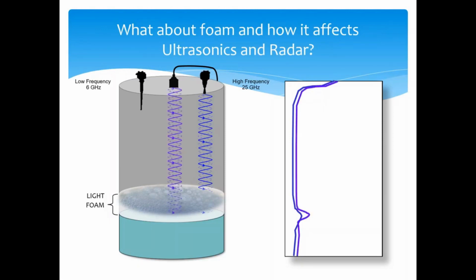When I do ultrasonic, I get a decent signal return here. That's probably a signal that I'd be able to work with. And in both of these cases, we're actually penetrating the foam here and giving you a true liquid level measurement. And then for my low frequency radar, I actually get a very similar signal return as I got when I had dense foam. So for our lighter foam, the low frequency radar is the best choice. And that makes sense because it's better at penetrating anything. It attenuates less, so it can penetrate that foam better, reflect off the liquid level below it. So low frequency makes the most sense for light foam.